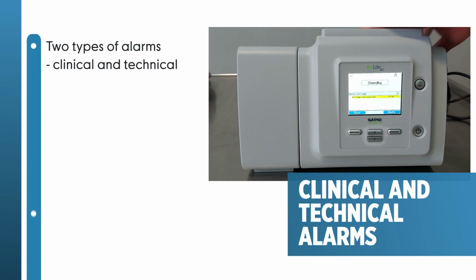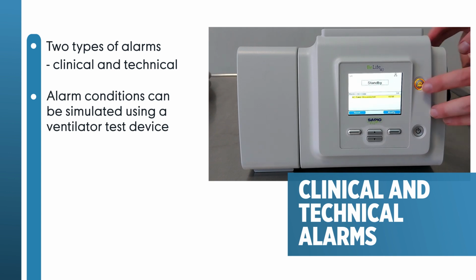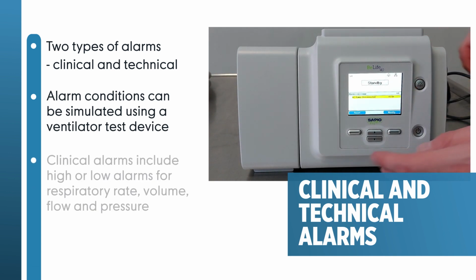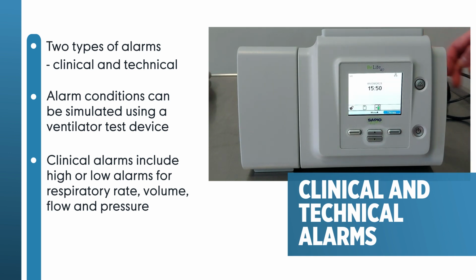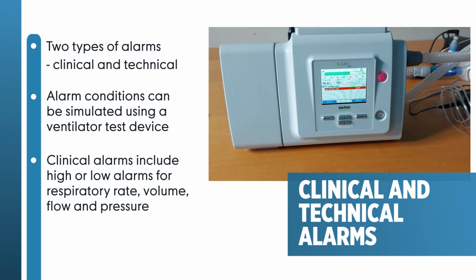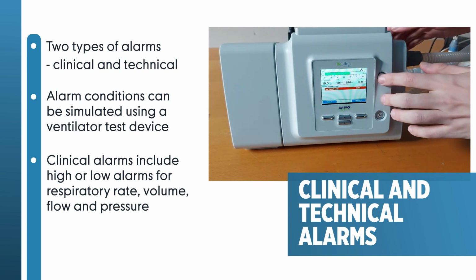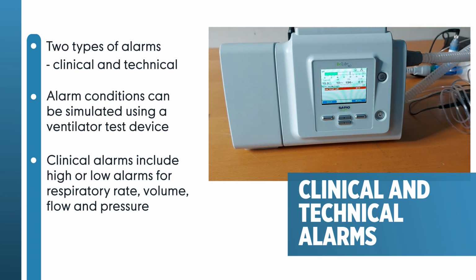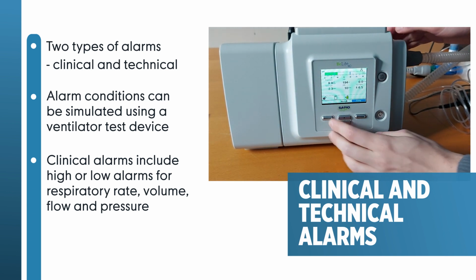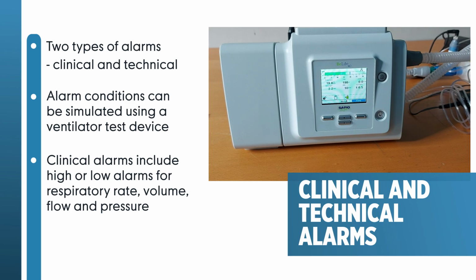There are two types of alarms, clinical and technical. Both alarm types should be verified by following the manufacturer's guidelines as they vary according to the device. Many alarm conditions can be simulated using the ventilator test device. Example clinical alarms include high or low alarms for respiratory rate, volume, flow, and pressure.